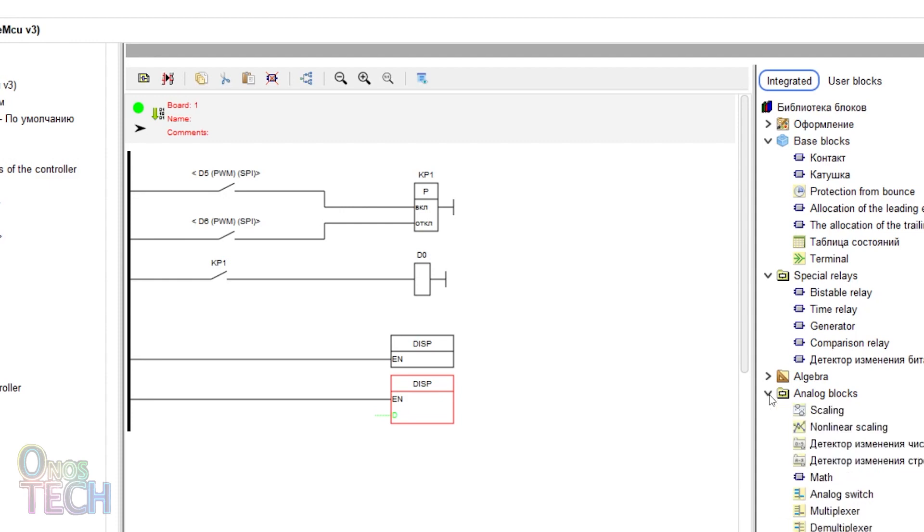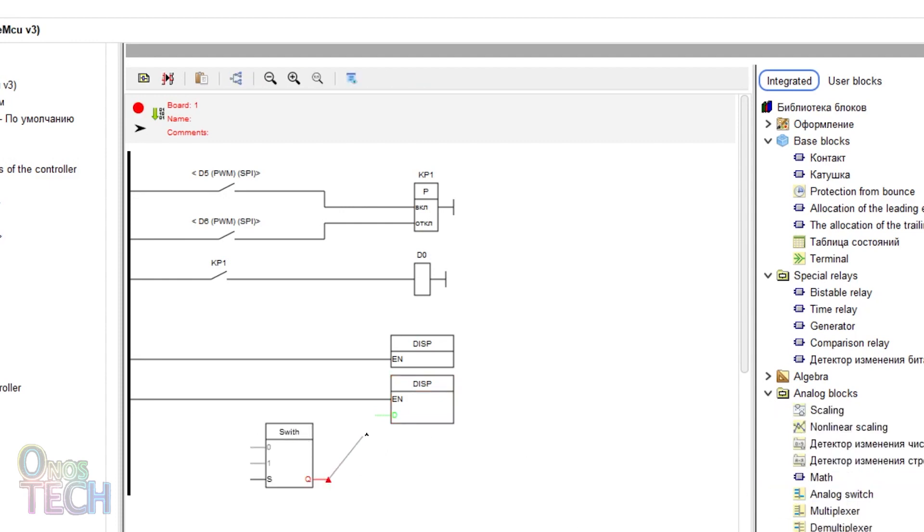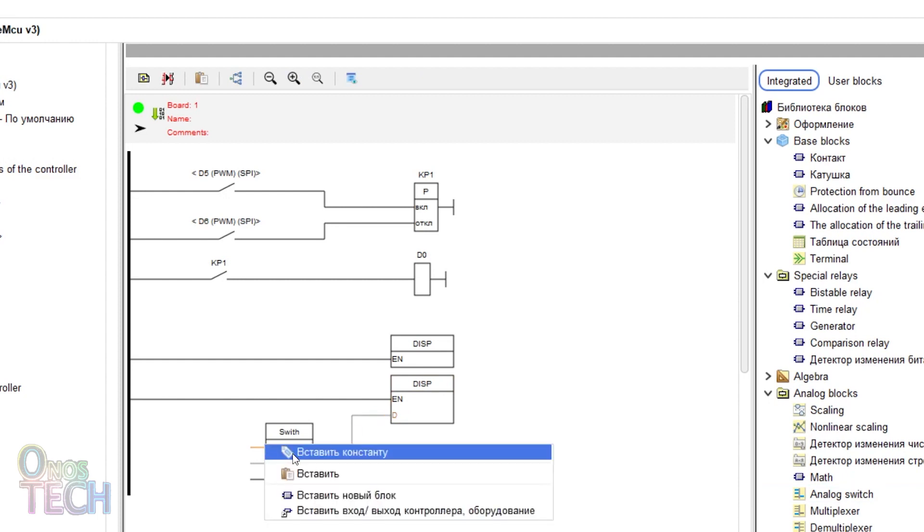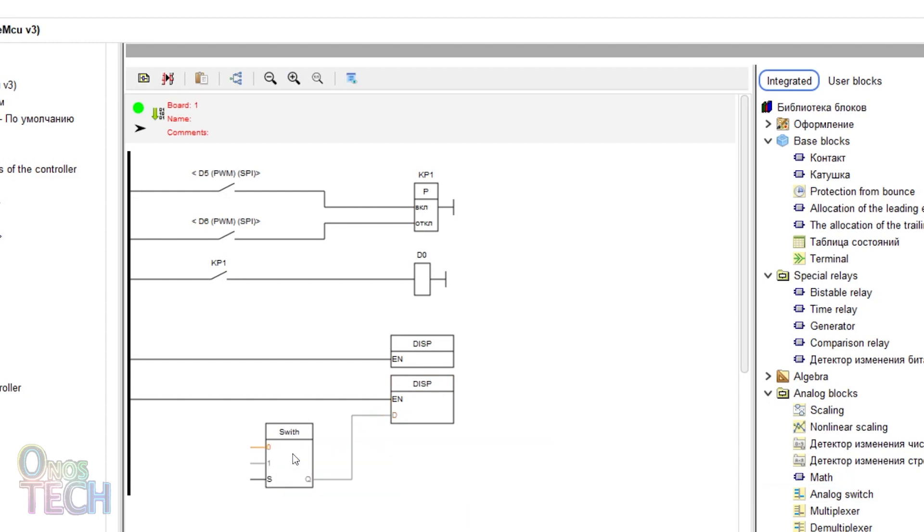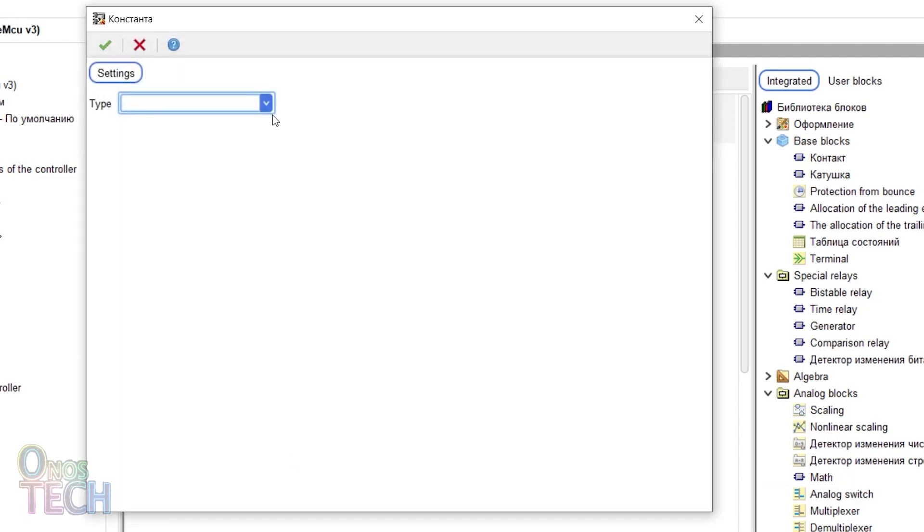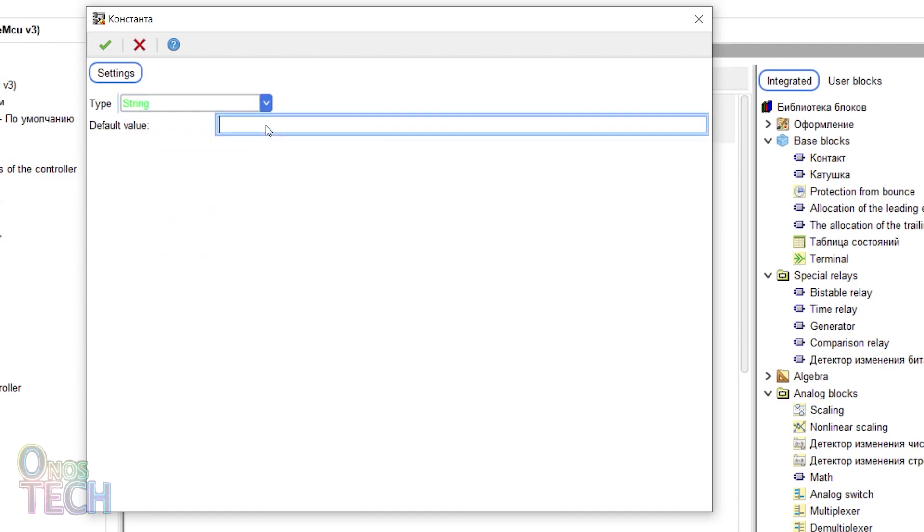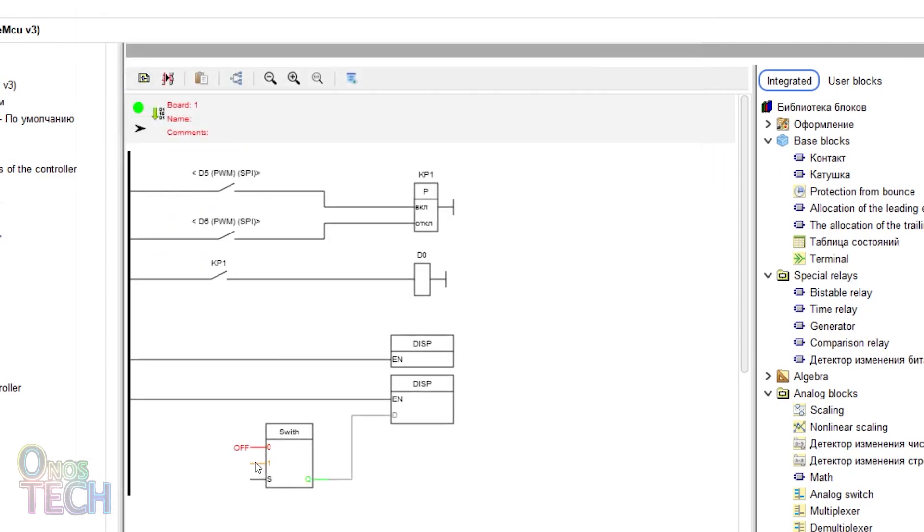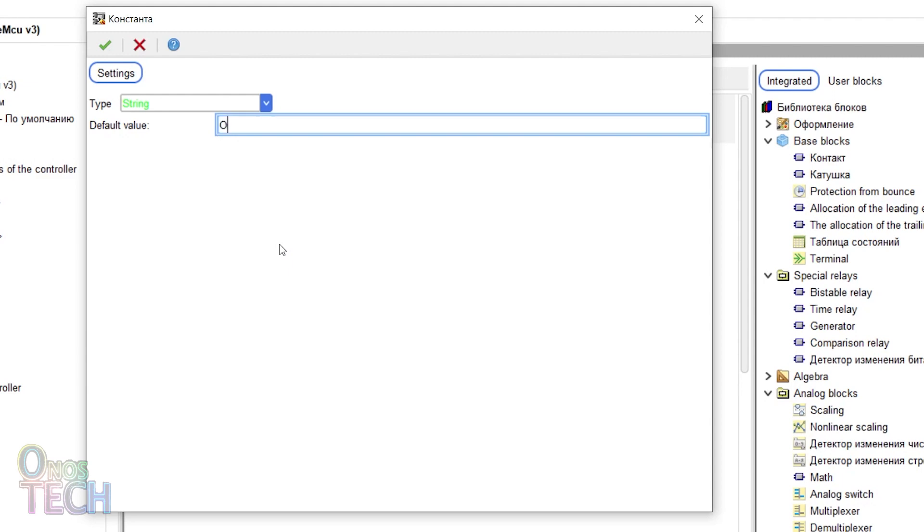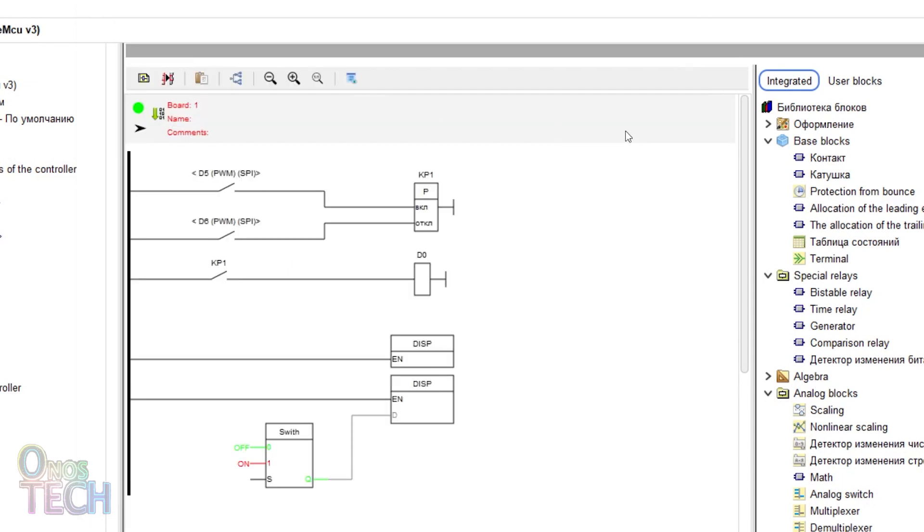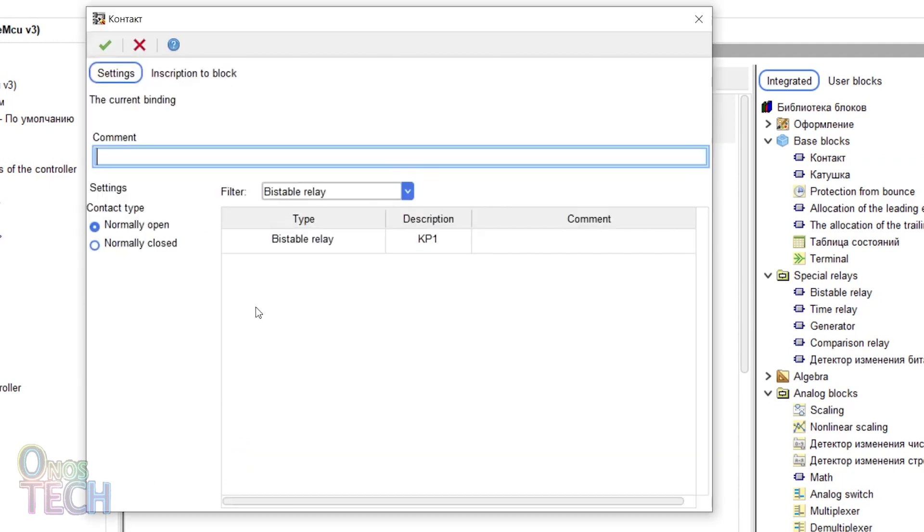Insert an analog switch block and connect its output to the input of the display. Right click on the zero input of the switch and select string type variable with the default value off. Set the one input default value to on. And connect the bistable intermediate contacts to the S input of the switch.